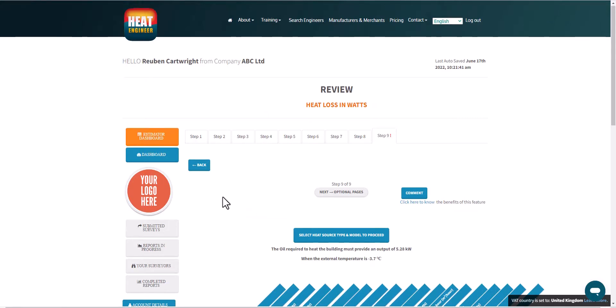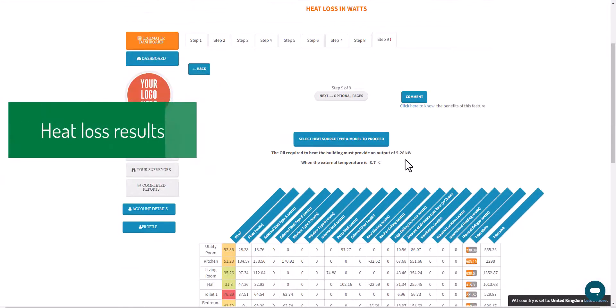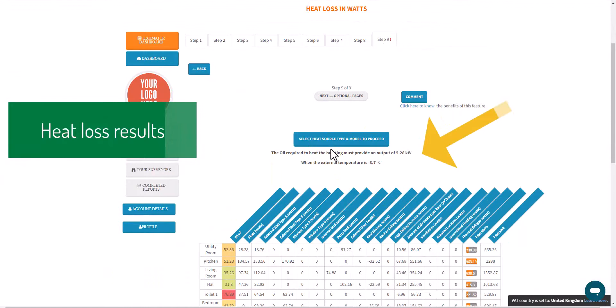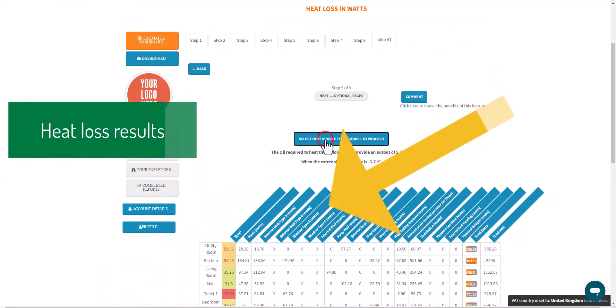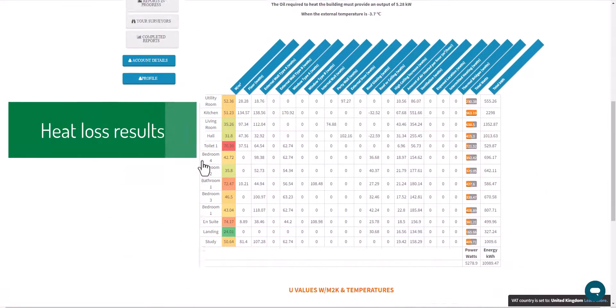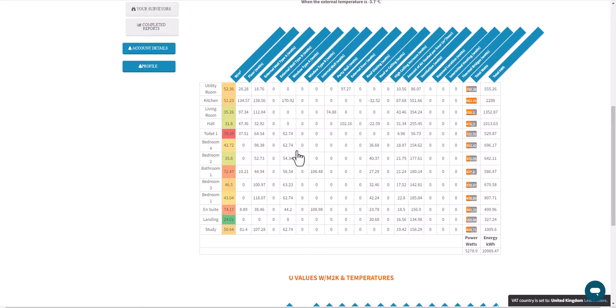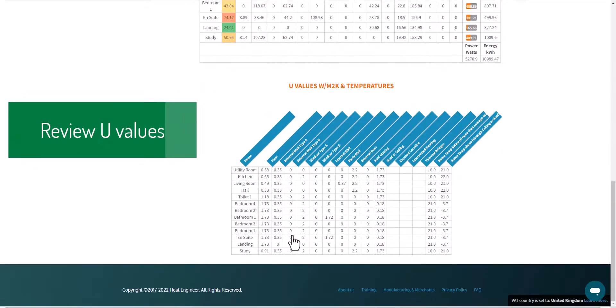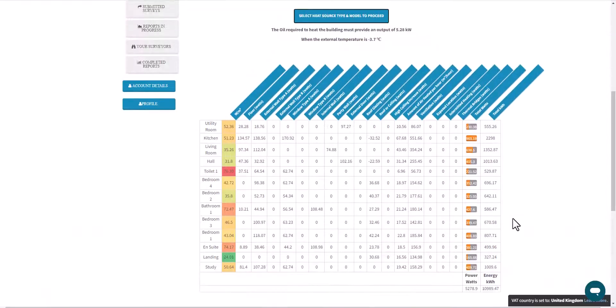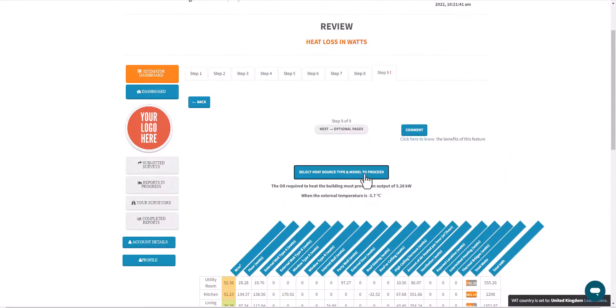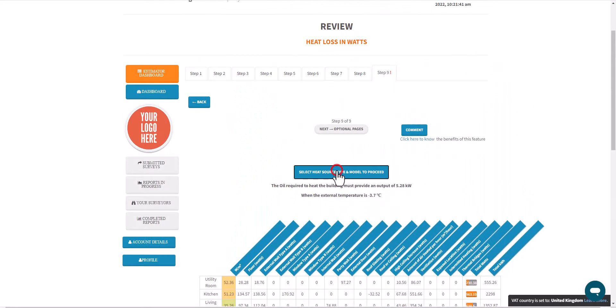On step nine we're reviewing the heat loss results. We've got an output of 5.28 kilowatts, we've got the watts per meter squared, we can see the worst performing room, in this case there's toilet number one, and down at the bottom we can see the overall results of the U-values and temperatures that have been used as well.